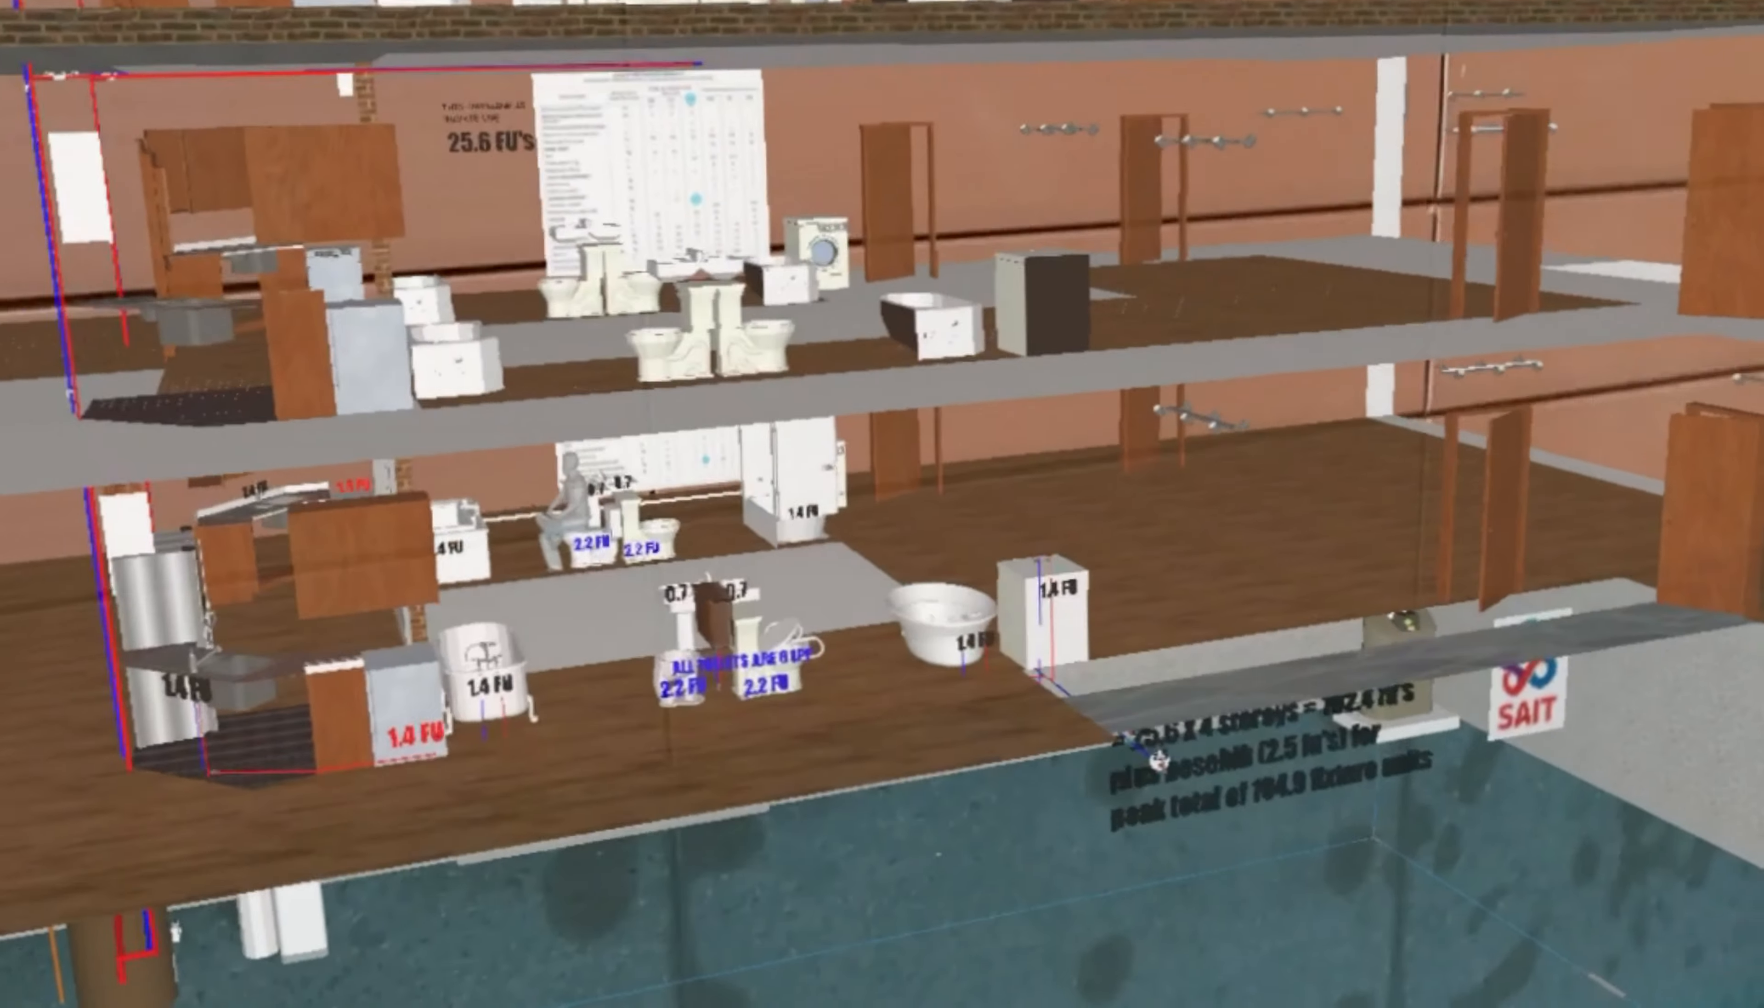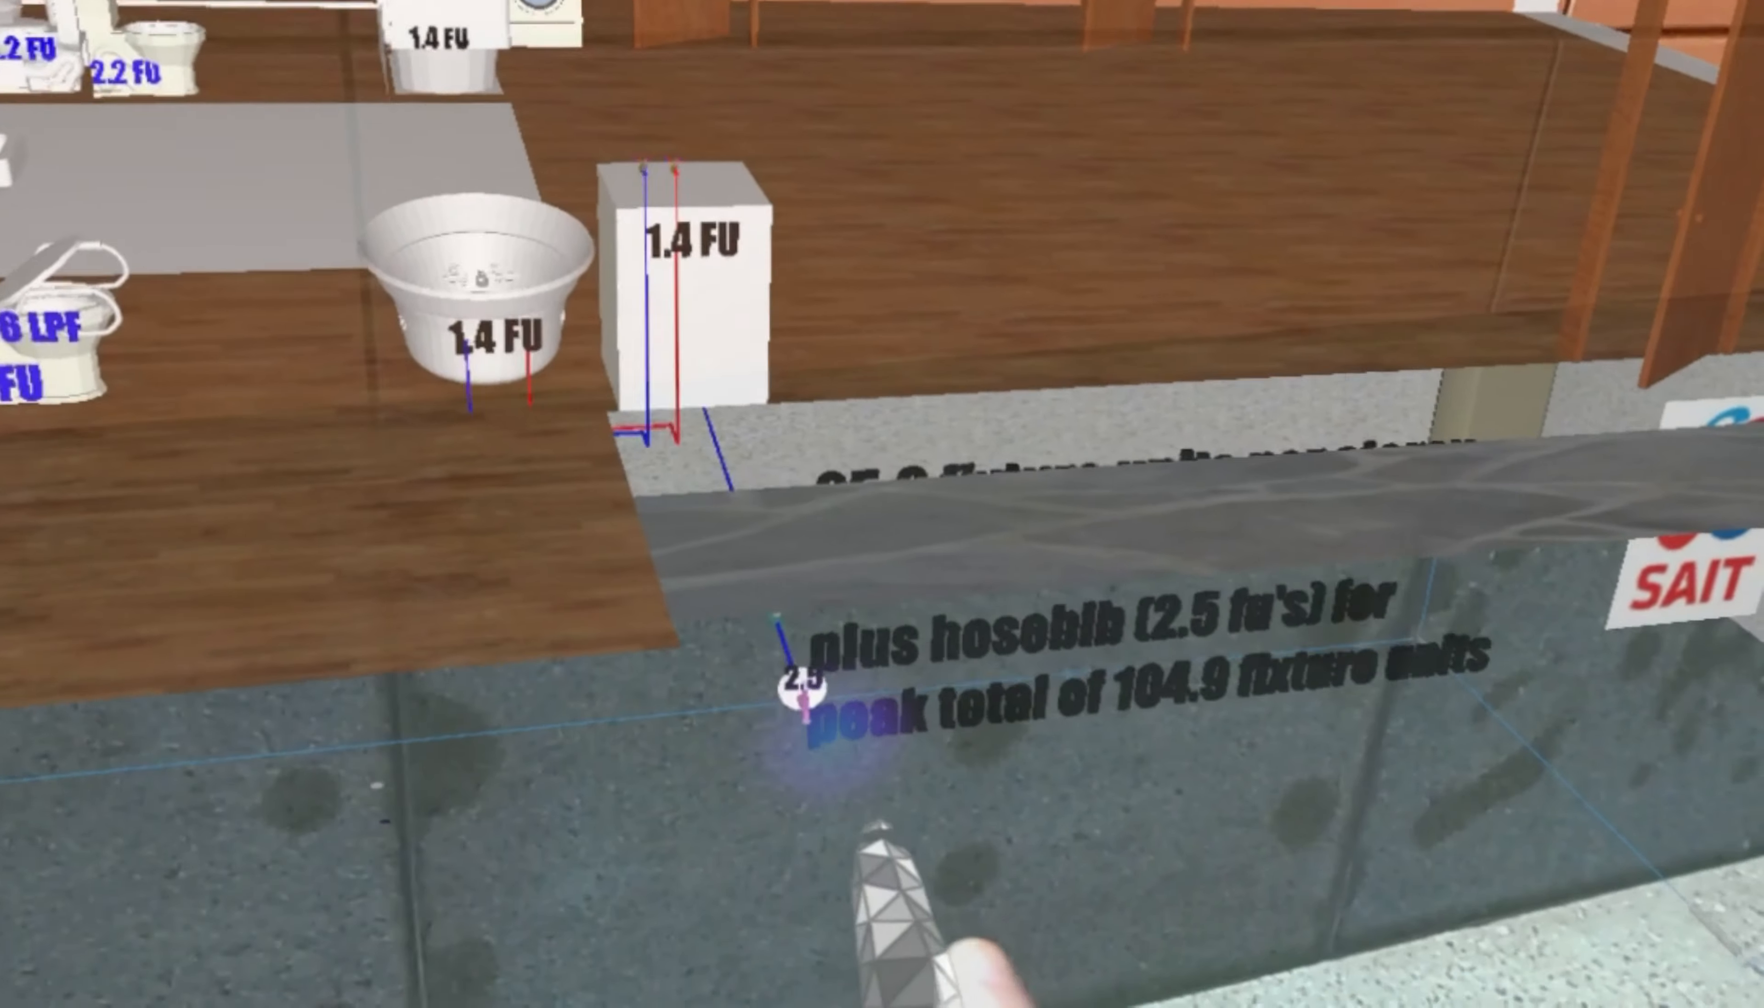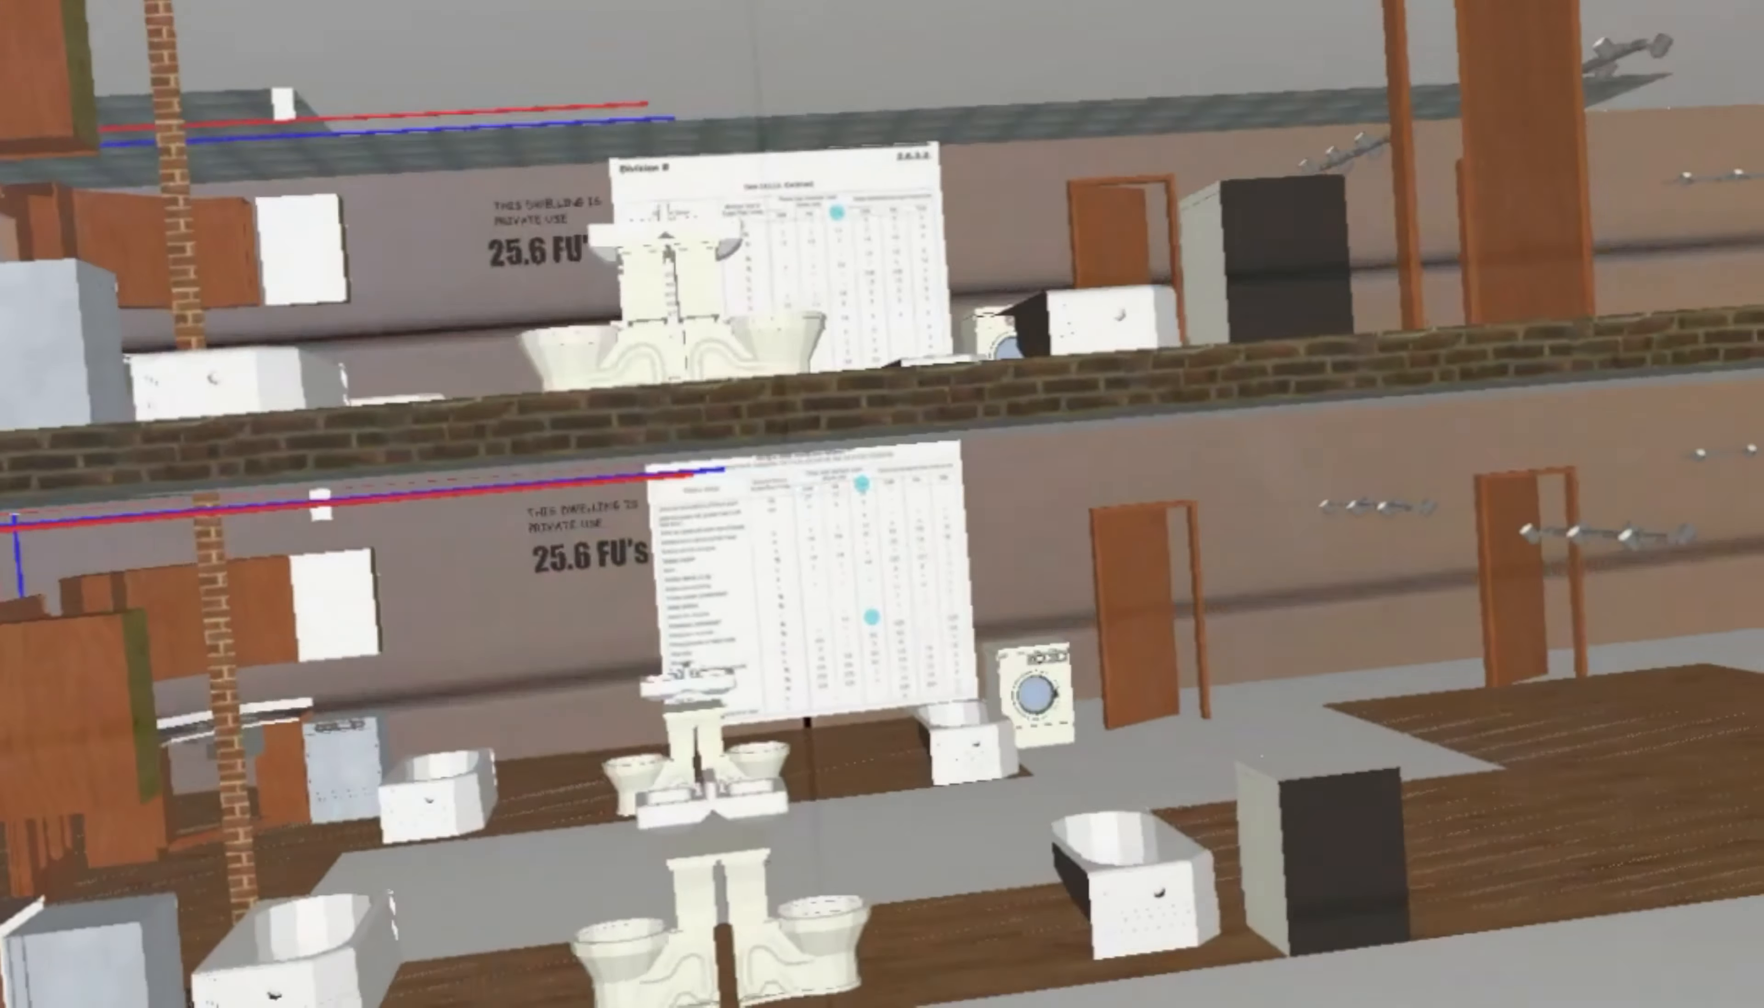Now we go into more detail because then there's also tables that tell you what the separate fixture unit loads of all these fixtures are. That's how I came up with 104.9. Like for instance, I had to add 2.5 because of this little hose bib right here that is for the lawn in the front. That's why I added that one. Anyhow it's 104.9.